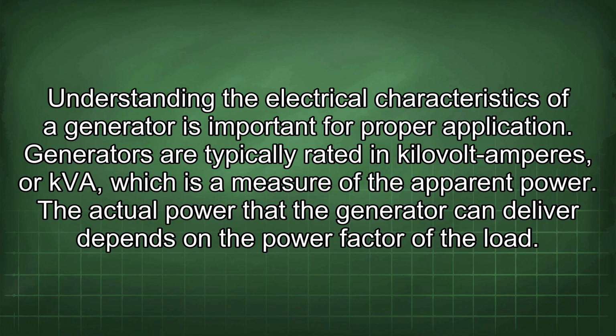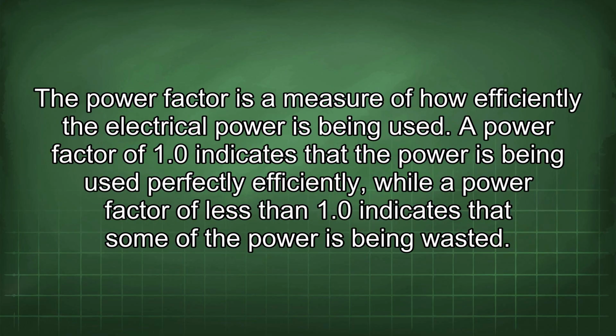Understanding the electrical characteristics of a generator is important for proper application. Generators are typically rated in kilovolt amperes, or kVA, which is a measure of the apparent power. The actual power that the generator can deliver depends on the power factor of the load. The power factor is a measure of how efficiently the electrical power is being used. A power factor of 1.0 indicates that the power is being used perfectly efficiently, while a power factor of less than 1.0 indicates that some of the power is being wasted.